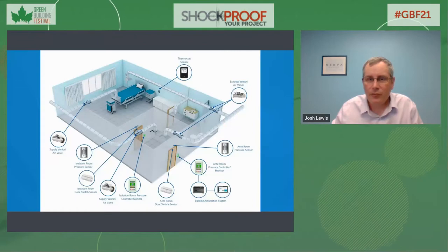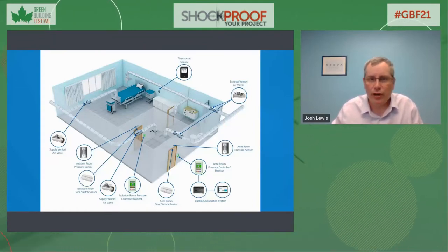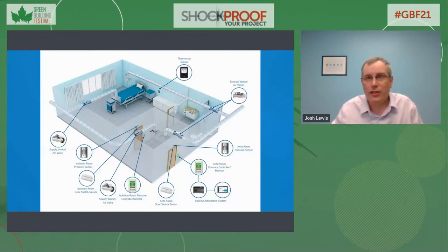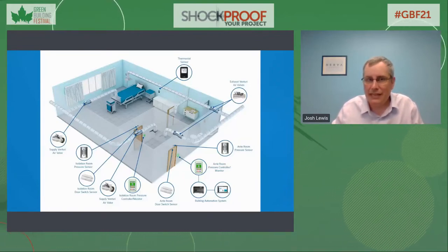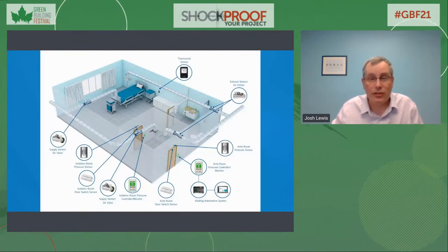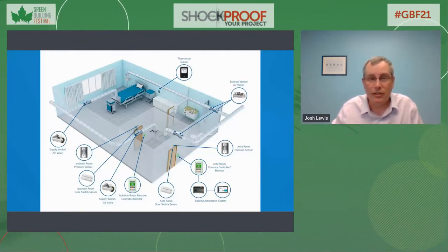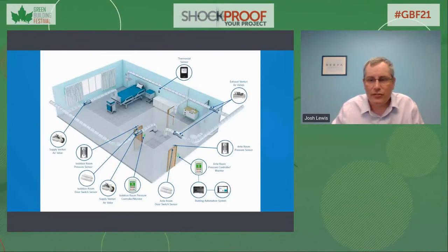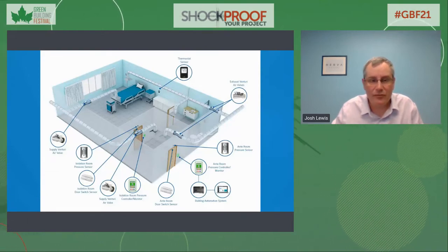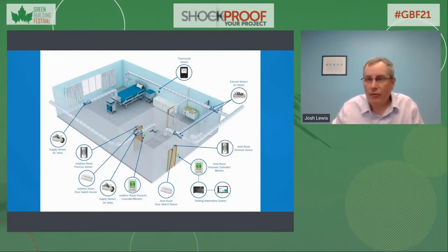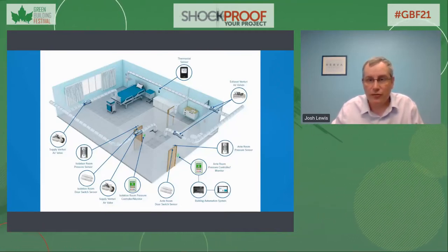in the wintertime. If we want to benchmark buildings that have above average indoor air quality, we need to look no farther than hospitals and other healthcare facilities. These types of facilities are mandated by codes and regulations to have HVAC systems that move large, constant volumes of air, bringing in a high percentage of fresh air into the building, and have tight filtration and humidity control. Why? Well, because years and years of research and experience has shown the healthcare sector that this type of HVAC configuration greatly reduces the risk of healthcare-acquired infections, such as pneumonia, staph, MRSA, sepsis, among others. However, virtually no other type of buildings are designed and constructed as healthcare facilities are, and if they were, their baseline energy consumption would be very high. The indoor air quality solutions for typical buildings must be different.